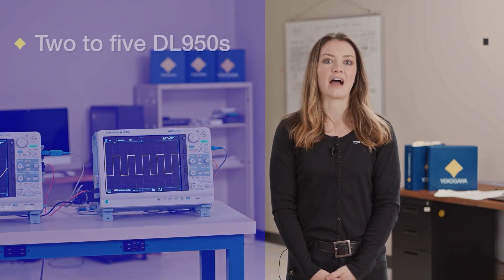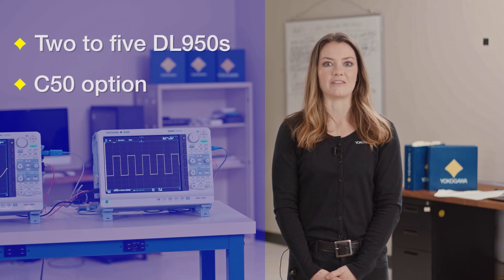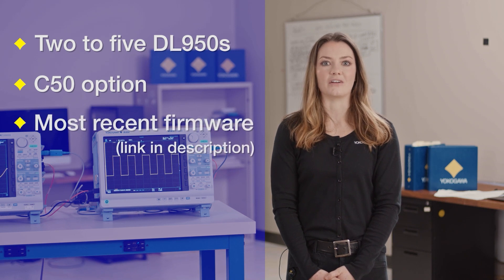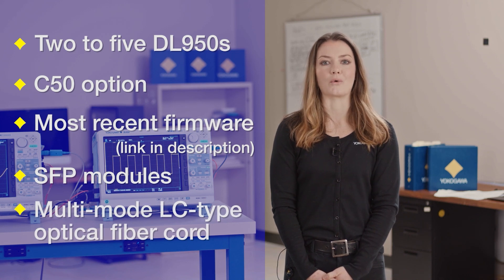For synchronization you will need two to five DL950s, the C50 option for each DL950, the most recent firmware installed, SFP modules, and a multi-mode LC type optical fiber cord.